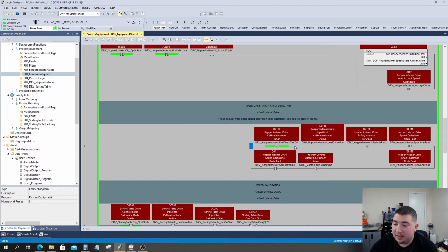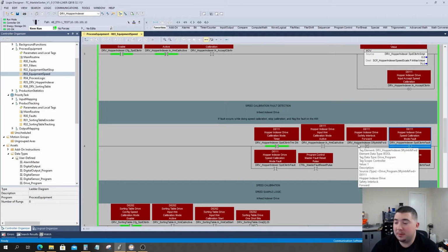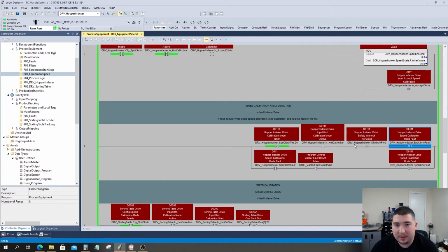In the event that we're doing a speed calibration but we lose our safety interlock, which is right here, then we'll latch a fault. This will stop the speed calibration and will throw an alarm so we won't be mystified by what happened. We'll get an alarm either way, but this way we'll get a secondary alarm saying that not only did the motor fail for some safety reason, but it also has failed the speed calibration and it will not accept any values.